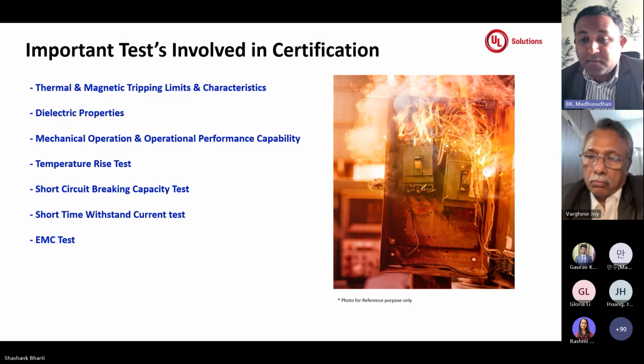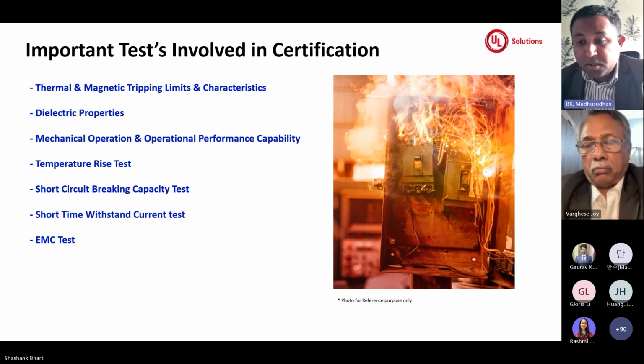The breaker has to withstand this for 30 minutes with the conductor and the load at the particular torque, and the conductors should not move out of the terminal, and any slippage will be looked at. This is followed by a pull test carried out on these terminals, basically to ensure the torque you have declared for the particular conductor. The standard has given a reference weight. We need to apply it for 1 minute, and we need to see there is no spillover of the conductor from the terminals. This will be looked at, because this is also a critical test.